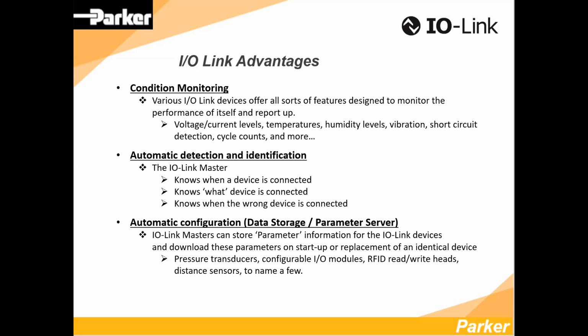Automatic detection and identification - think about a traditional sensor. You didn't know if it fell off, got cut off, or if somebody took it off and used it somewhere else and didn't replace it. With IOLink, not only do you know if an IOLink sensor is connected, you know exactly what IOLink sensor is connected. So now in error-proofing the PLC, you can put up a diagnostic that there's a port mismatch at whatever master, whatever port - the correct IOLink device or sensor is not connected to the right port. It's just that intelligence being built in.